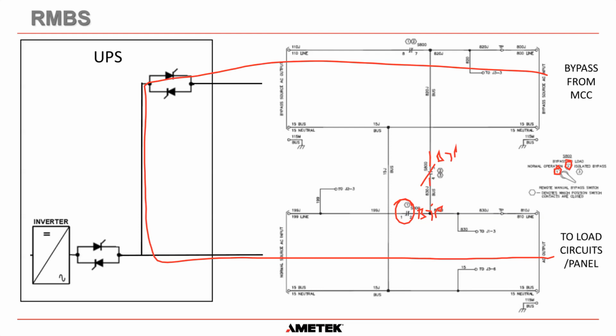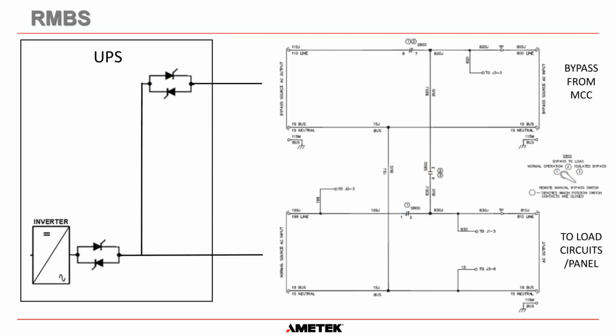So in that circumstance, when we move to bypass to load, what happens is power flows through here, down through this contact, excuse my terrible drawing, and out through here. Now remember, this is now open, so no power flows out that way anymore. Okay? This terminal does not have power because of that switch. And the great thing about an RMBS is the isolated bypass position.